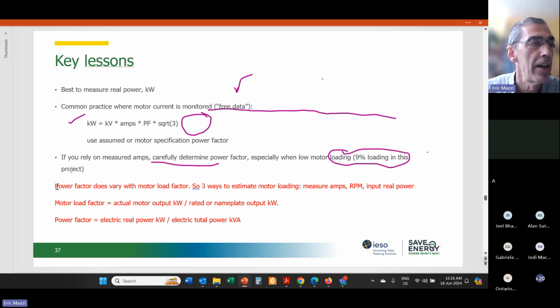I guess Sky asked a question: can you use power factors on an electricity bill? Generally, no. You would want the power factor for the specific piece of equipment that you want to measure. If it so happens that, let's say, this 500 horsepower motor was a very high proportion of the total load on the utility meter, then sure, you could do that, but that is not the case here. You want to get the power factor for the specific motor or loads of interest that you're going to do measurements on.